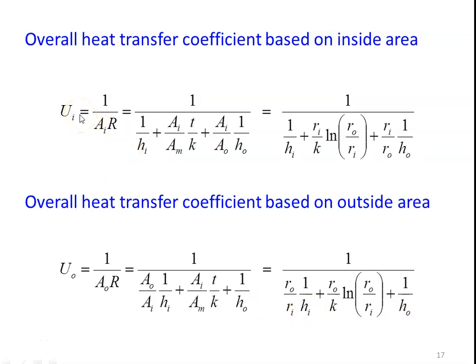In heat exchanger design, the overall heat transfer coefficient U value will typically be given directly. The overall heat transfer coefficient combines the inside convection resistance, the conduction resistance across the metal surface, and the outside convection resistance — three resistances combined together into one overall heat transfer coefficient.